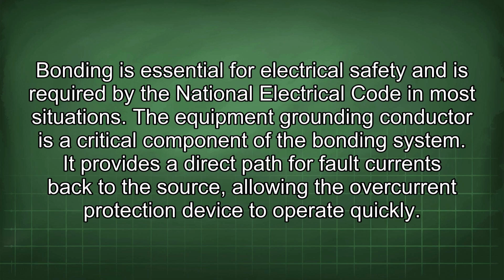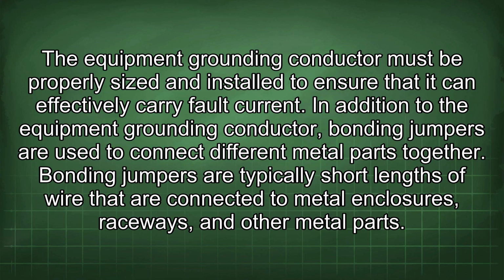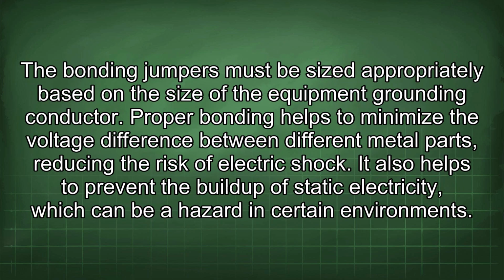It provides a direct path for fault currents back to the source, allowing the overcurrent protection device to operate quickly. The equipment grounding conductor must be properly sized and installed to ensure that it can effectively carry fault current. In addition to the equipment grounding conductor, bonding jumpers are used to connect different metal parts together. Bonding jumpers are typically short lengths of wire that are connected to metal enclosures, raceways, and other metal parts. The bonding jumpers must be sized appropriately based on the size of the equipment grounding conductor.